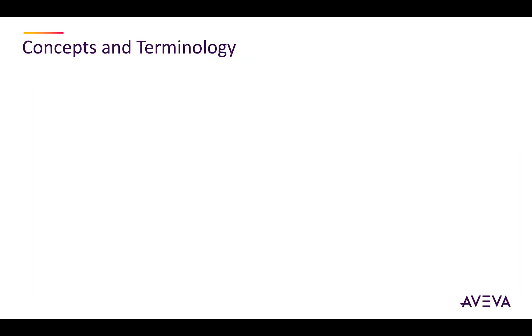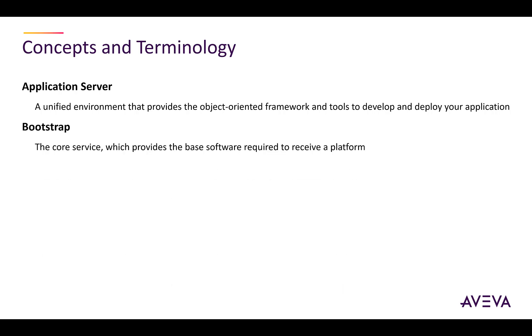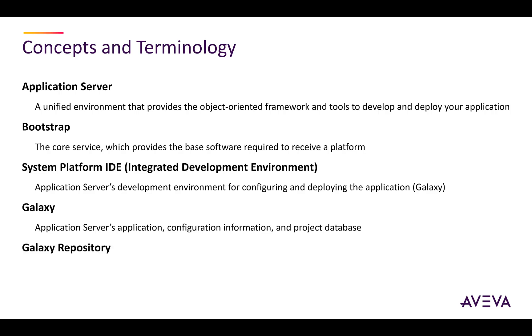To understand System Platform, it is really important to know some key concepts and terminology. First is Application Server — the environment that provides the object-oriented framework and tools to develop and deploy your application. Next is the bootstrap, the core service which provides the base software required to receive a platform. Next is the System Platform IDE, or Integrated Development Environment, where you configure and deploy the application, known as the Galaxy. Galaxy is the application that contains the configuration information and is the project database. Galaxy Repository is the computer and software that hosts and manages the Galaxy.